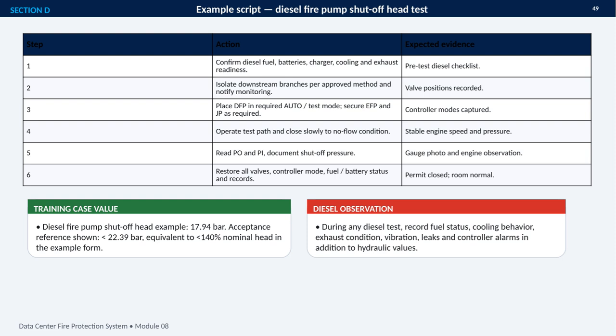The final step is restoration. Return valves, controller modes, fuel and battery status, and records to their normal condition. Diesel observation must include more than hydraulic readings: fuel status, cooling, exhaust, vibration, leaks, and controller alarms.